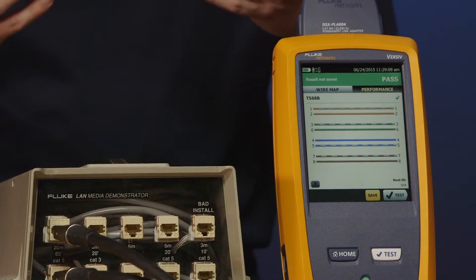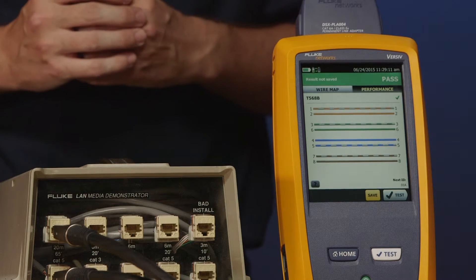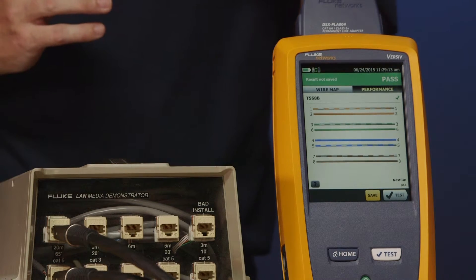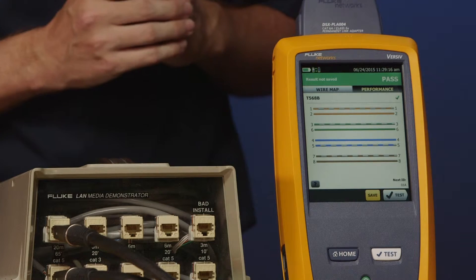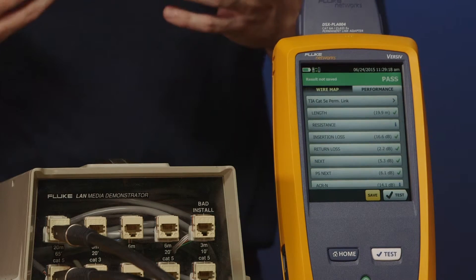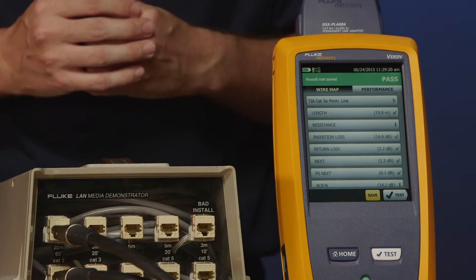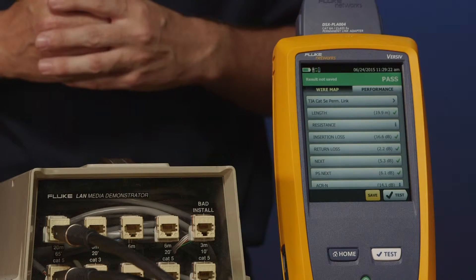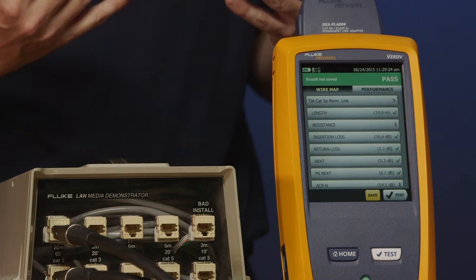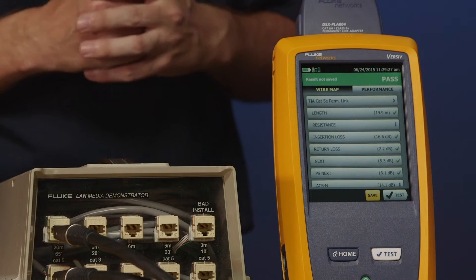So this tester passed. We see the pass on the top right hand corner. The first thing that we see on there is wire map. Amanda, go ahead and tap performance for me. Now we see what's very familiar to DTX owners is all the various parameters required for Cat 5e. Everything passes here, so we're good. Go ahead and hit save.